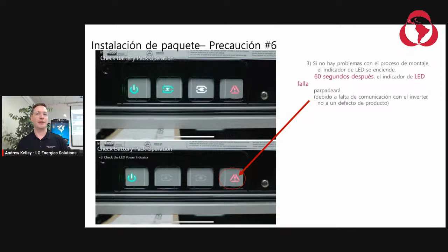I'm not going to review all of this, but you guys can take a look on your own time. If you leave the batteries installed but not operating for a long period, this is what could happen to the state of charge. So be advised, if you leave the battery breaker on and the inverter off, this gives you an idea of how long you have before you need to turn the solar inverter or grid back on to charge your batteries again. This is basically leaving it in standby mode but with most other equipment off. The battery will still slowly drain if it's hooked up and turned on.